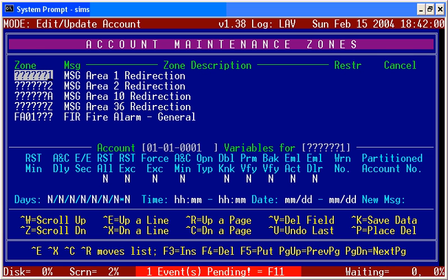In this last character of the transfer coming over from the receiver, within the SIMS2 interrupt-driven protocols we will combine the area identifier and the actual zone itself. So we can take up to the first 6 characters to identify any information about a zone, but the last character will be the area identifier.